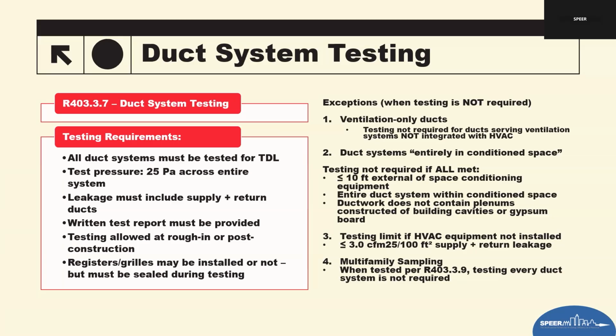The party performing the test, usually a third party, must provide a written report to the code official. This helps standardize documentation and close out the permit records. Testing is allowed at rough and/or final post-construction. The code is flexible on whether registers and grills are installed. The key is whatever is installed, you need to seal it. So we need to tape those things up. You'll either see it taped up at the time of pre-drywall for testing at rough-in, or you may not see the tape if they're in and out doing duct testing at final.